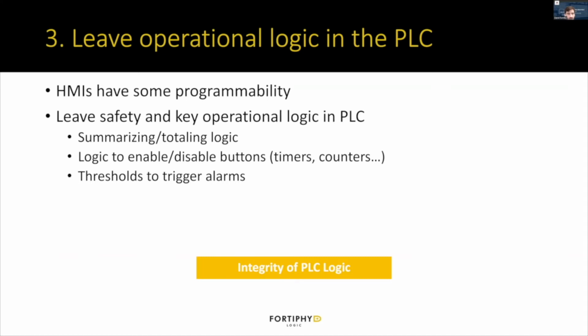Moving on to practice number 3, which is leave operational logic in the PLC. Some HMIs have pretty high level programmability, and so it may be tempting to add a lot of logic to the HMI itself, but just make sure the logic you're adding to the HMI is not key to the safety and key to the operation of the physical process, because the HMI is more likely to be compromised than the PLC itself. And having the key safety features, the key operational logic in the PLC makes it harder for the attacker to compromise that. Specifically, some of the things that are maybe tempting to put on the HMI are summarizing and totaling logic, logic to enable and disable different buttons, and thresholds to trigger alarms. All those are sometimes put on the HMI, but putting them in the PLC does make it a little harder for attackers to mess with.